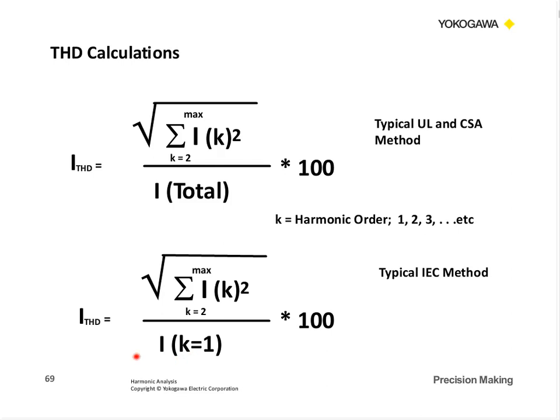It's math, so they will be different. The total value is going to be higher in many cases than the fundamental. So we're going to divide by a higher number, and so it could give you a lower reading just because of the way we do the math on the THD, which is correct. Well, you've got to remember, it's just a math reference. But we give you both methods to be able to calculate.